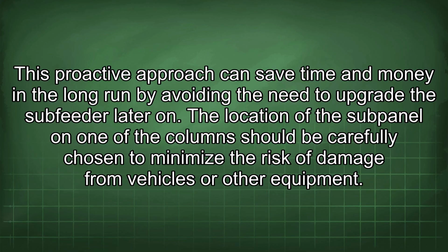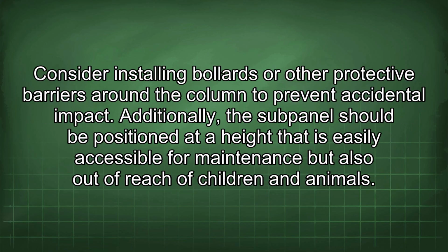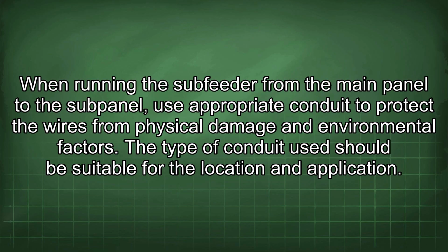The location of the subpanel on one of the columns should be carefully chosen to minimize the risk of damage from vehicles or other equipment. Consider installing bollards or other protective barriers around the column to prevent accidental impact. Additionally, the subpanel should be positioned at a height that is easily accessible for maintenance but also out of reach of children and animals. When running the subfeeder from the main panel to the subpanel, use appropriate conduit to protect the wires from physical damage and environmental factors.